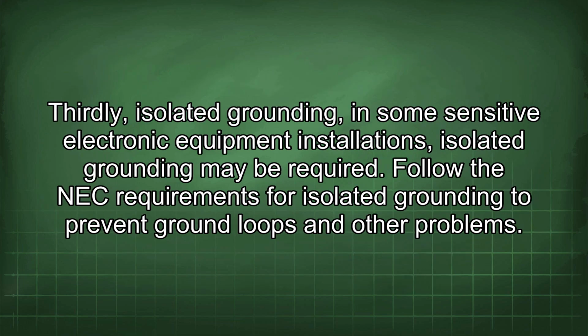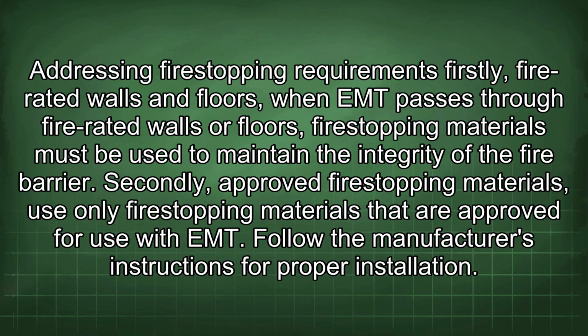Thirdly, isolated grounding. In some sensitive electronic equipment installations, isolated grounding may be required. Follow the NEC requirements for isolated grounding to prevent ground loops and other problems. Addressing fire stopping requirements. Firstly, fire-rated walls and floors. When EMT passes through fire-rated walls or floors, fire-stopping materials must be used to maintain the integrity of the fire barrier. Secondly, approved fire-stopping materials. Use only fire-stopping materials that are approved for use with EMT.